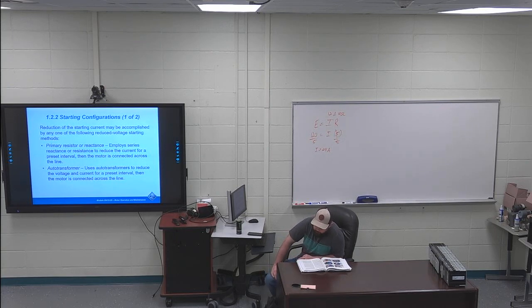I do have the second bullet point in the bottom right of page 5, just the first sentence highlighted. Auto transformer starting uses auto transformers to reduce the voltage and current on the first step. So auto transformers can be used to start motors at a reduced voltage and current. Going on to page 6, they have part winding. The last bullet point in that section is highlighted.